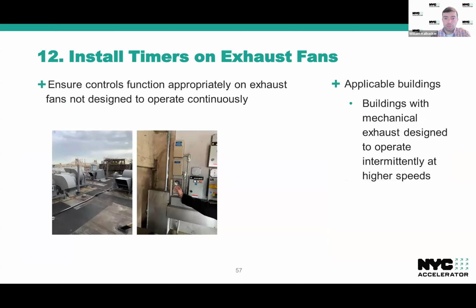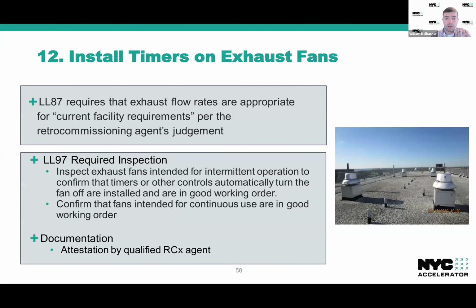Measure number 12 revolves around exhaust fan timers. For buildings that have mechanical exhaust, where those exhausts are designed to operate intermittently, it's important to make sure that they are operating as designed and not operating constantly, so that you do not use energy unnecessarily. So this measure revolves around ensuring that the timers and controls on fans are working properly.